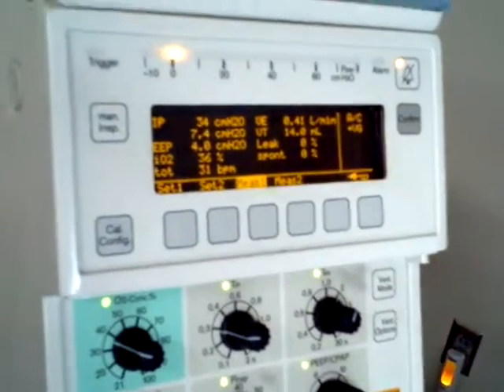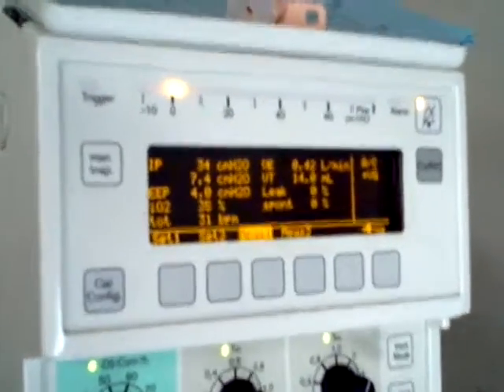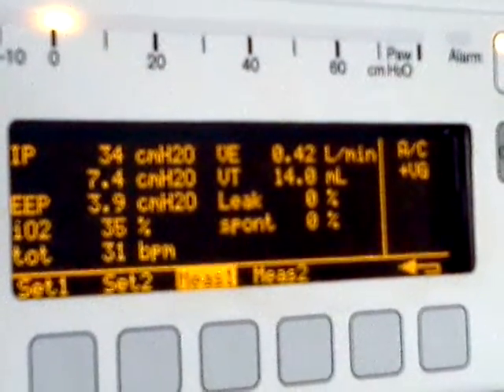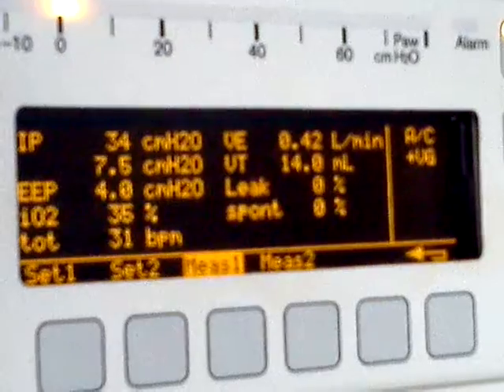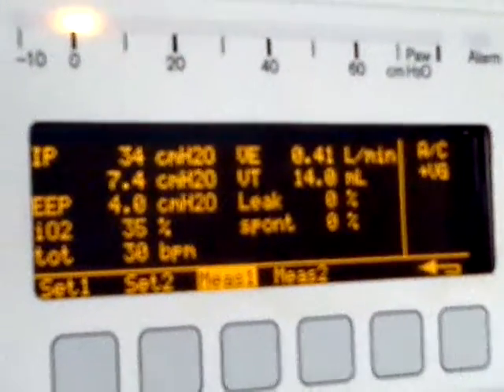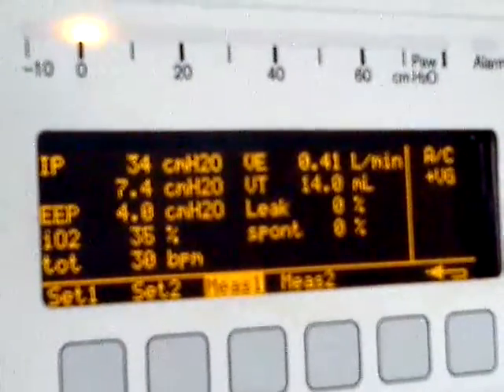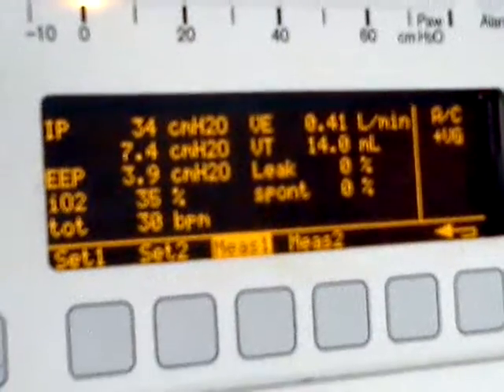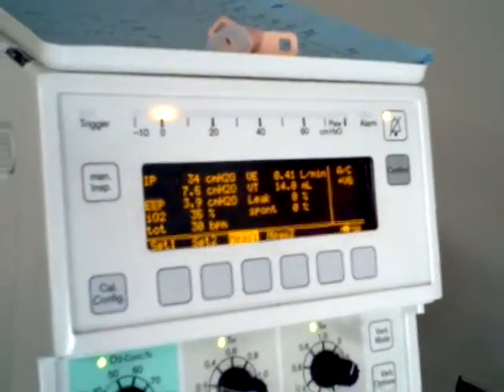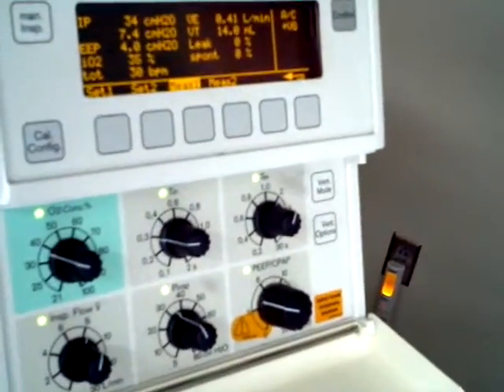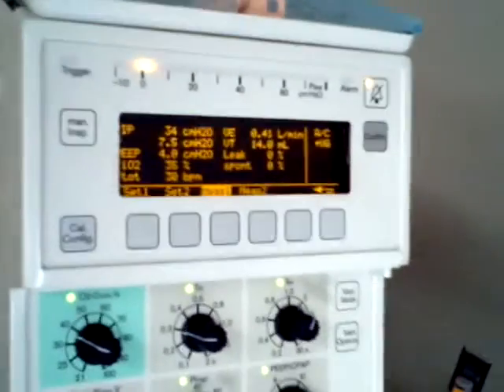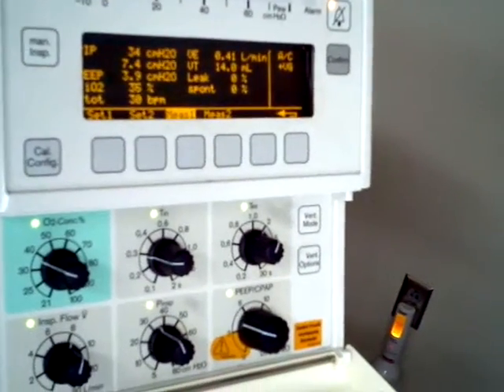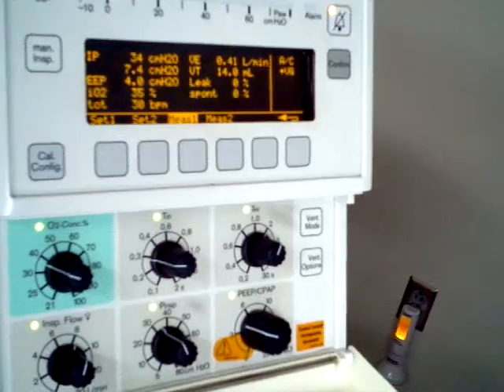What kind of peak pressure is it requiring to get a tidal volume of 14? 34, okay? Which is a lot. This is almost like PRVC now. Do I want to give a little cushion that if the ventilator has to raise that PIP anymore, it can do it? This is where I dial in about a cushion of 2 or 3 centimeters of water. So I know it's taken 34 to get what I want.